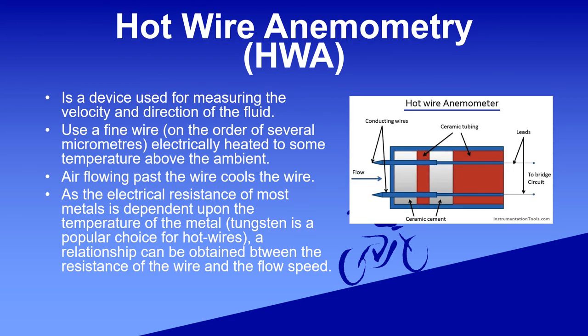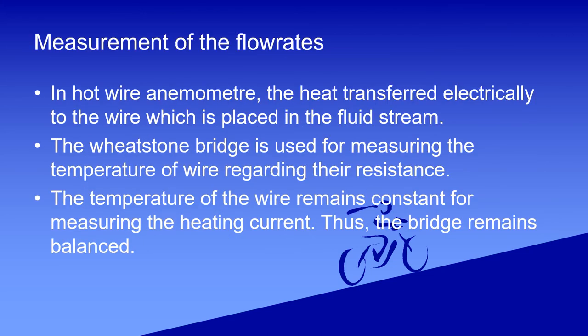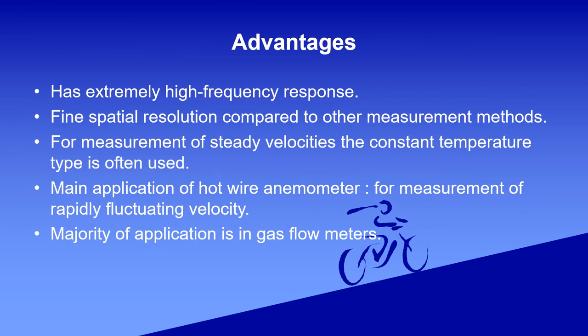The last device is Hot Wire Anemometry, used for measuring the velocity and direction of fluid. It uses a fine wire on the order of several micrometers, electrically heated to some temperature above ambient. The air flowing past the wire cools the wire. In hot wire anemometry, the heat is transferred electrically to the wire, and a Wheatstone bridge is used for measuring the temperature of the wire.